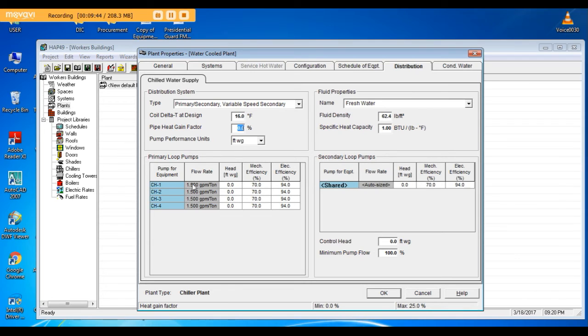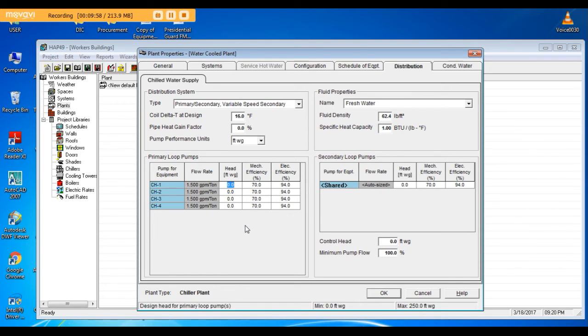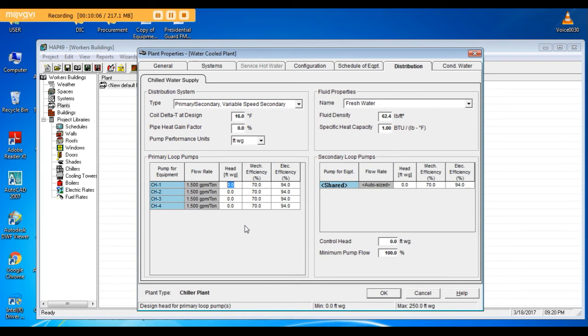Let's define the head of each pump, the head of the primary pumps. That means the required head to cover the friction losses from the primary pump including the chiller to the suction of the secondary pump. Our design head for primary pumps is 70 feet.